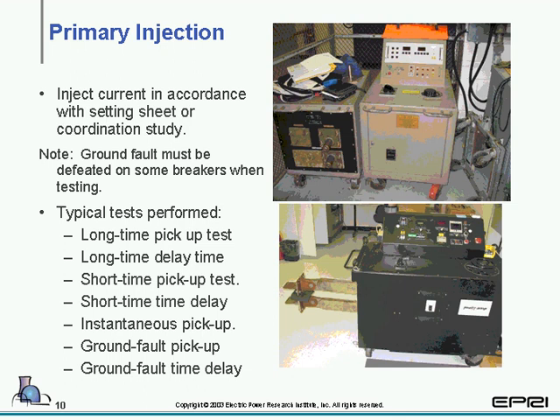Now, you have to use the coordination studies designed by the manufacturer to verify if they're within their band. We're looking at these basic typical tests. Quite often, people who test this breaker will choose a value, normally 300% of the rated current of the protection device, and then shoot it and make sure it's in that time band. That is only one test.